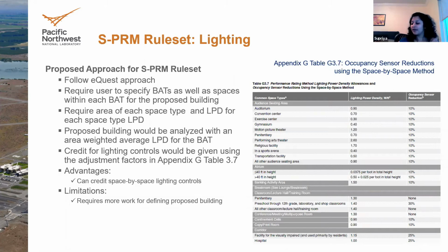Right, so you mean just to be able to know the impact of daylighting, Gail? Daylighting, and also to account for loads that vary in spaces in terms of impact on HVAC. Right. My thought, if we're implementing daylighting, is that you'd just identify the percent of each space that's in the primary or secondary daylit zone, and then get credit for that percentage of the lighting.